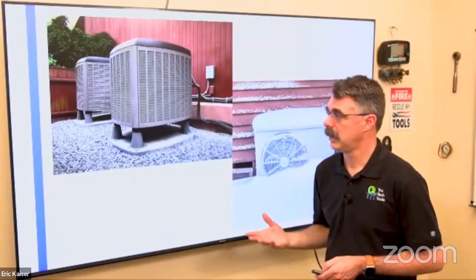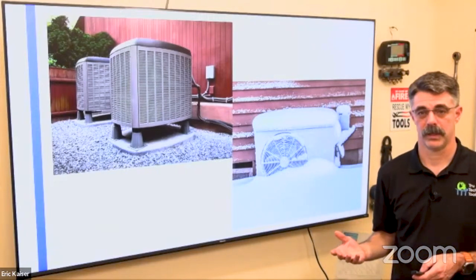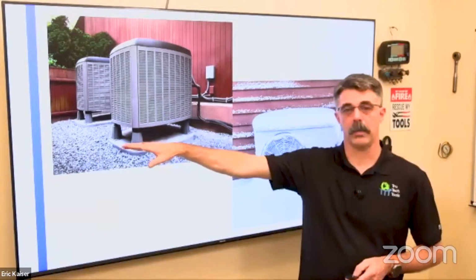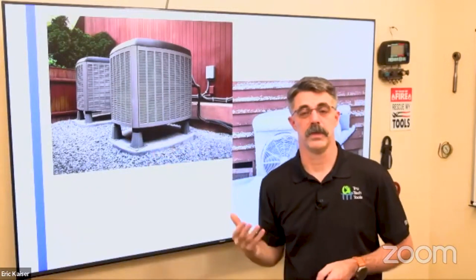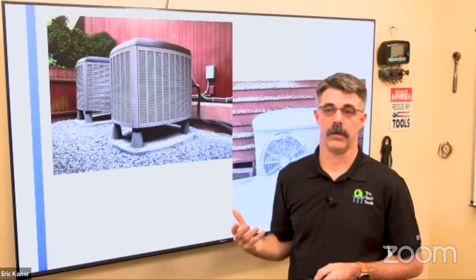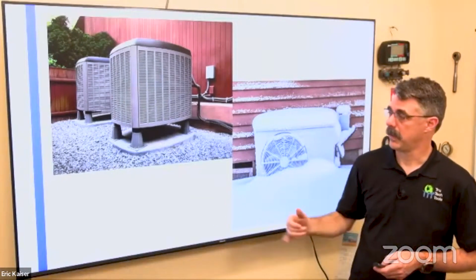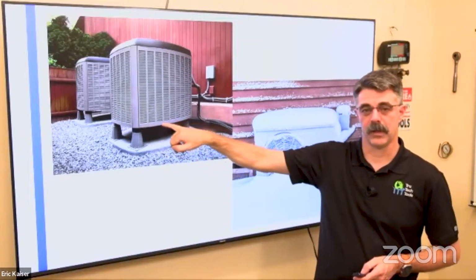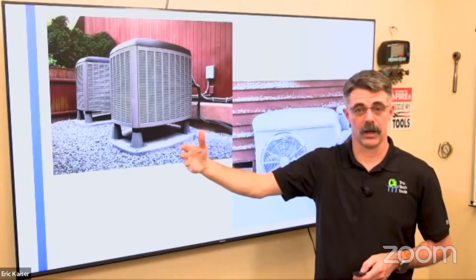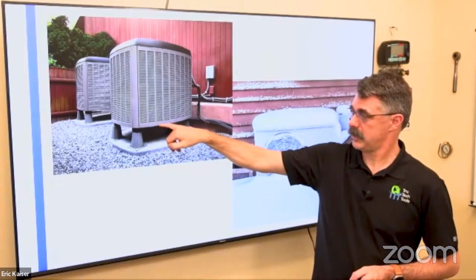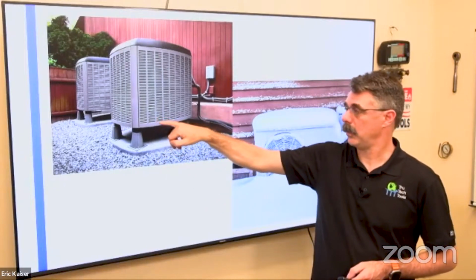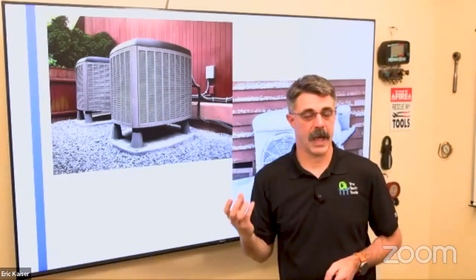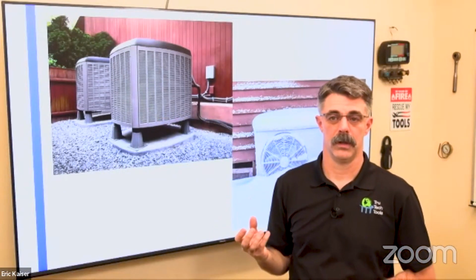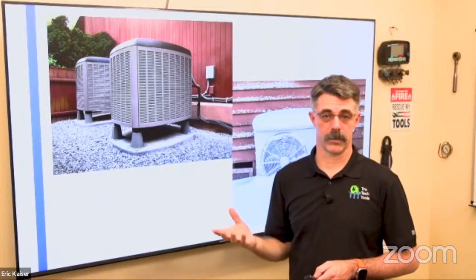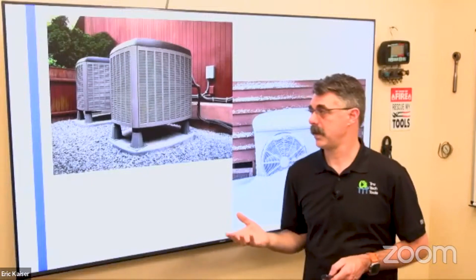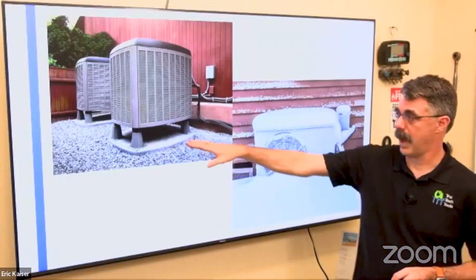We also need to consider how we're going to get them up, right? This is great. This is how we want heat pumps. We want them sitting up off the ground. A lot of the reason for that is because of the water that drains off of them when they go through the defrost cycle. If that builds up in the bottom of the cabinet, it creates hard ice or clear ice, and it will eventually build up far enough that it will freeze and break the bottom passes of the refrigerant coil. And then you have a leak of refrigerant in the middle of winter, and the owner's not real happy because you probably just destroyed that unit because it's not up on pump ups.